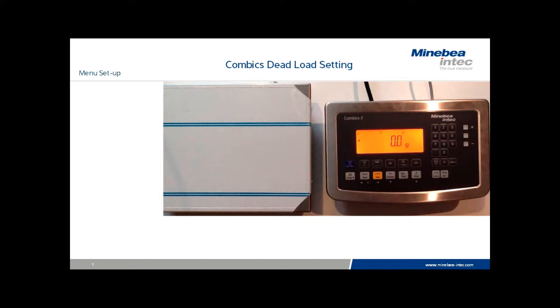To begin the process, we need to reassign the function of the ISO test key. We do so by entering the menu, and that's accomplished by turning the scale off, back on, and then pressing the tare key during the digit check.